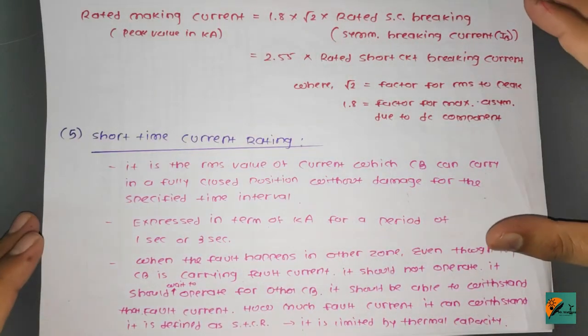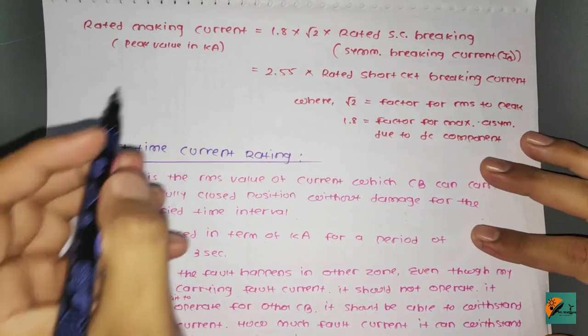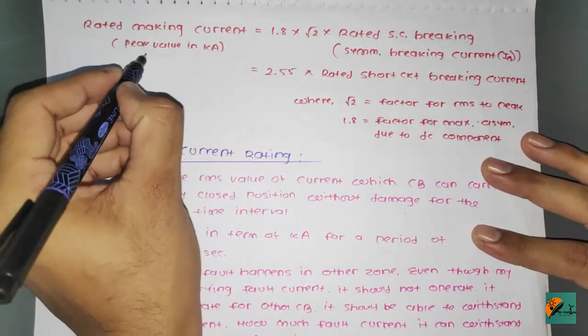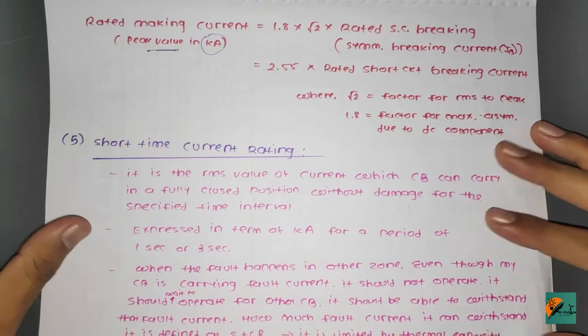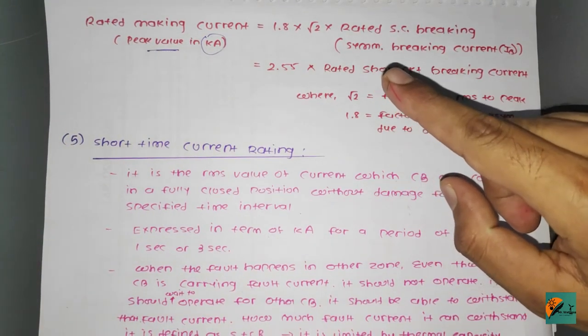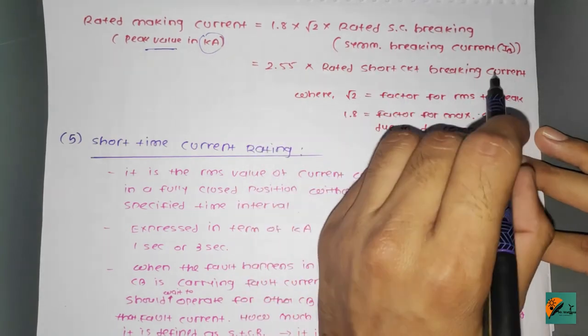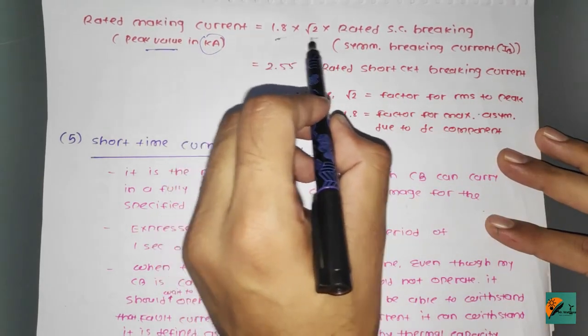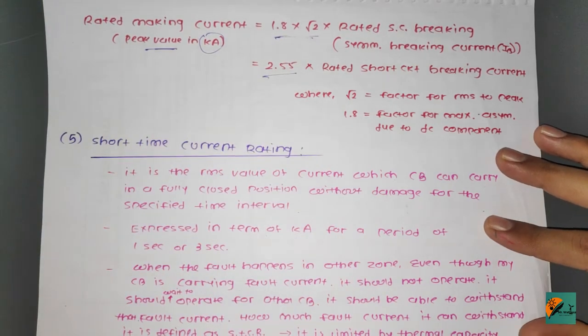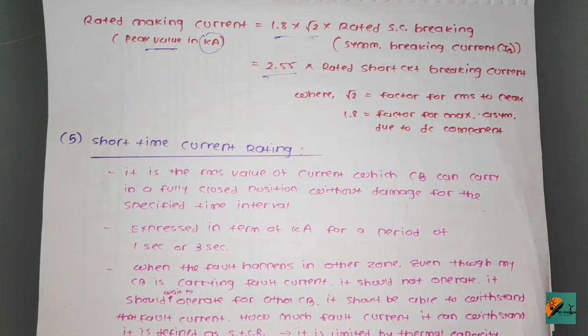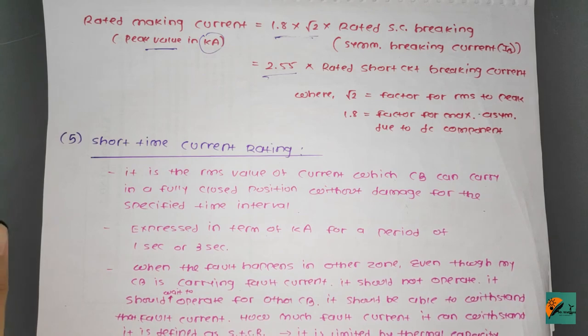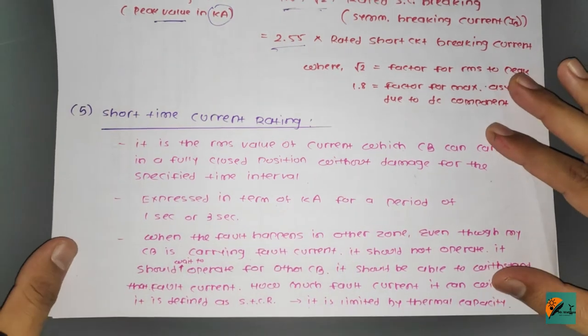The circuit breaker should be able to close without difficulty and withstand the mechanical forces developed during closure. This is checked by carrying out a making current test. The rated making current equals 1.8 × √2 × rated short circuit breaking current = 2.55 × I_b, where √2 is the RMS-to-peak factor and 1.8 is the factor for maximum asymmetry due to the DC component.